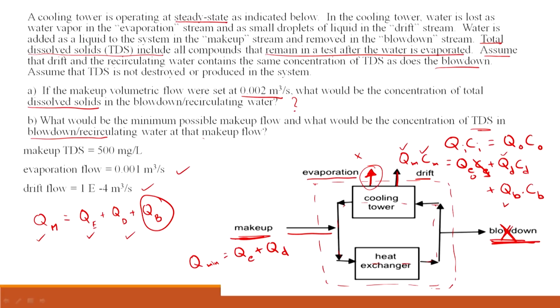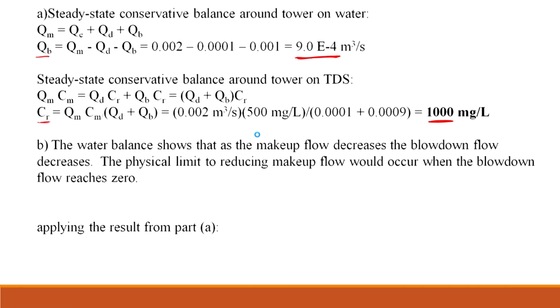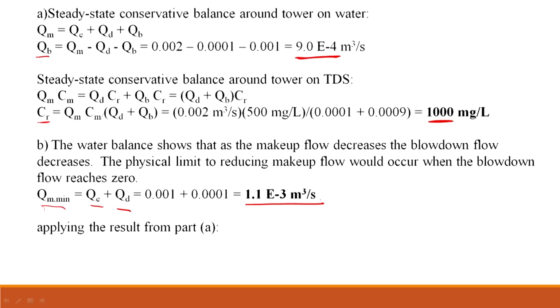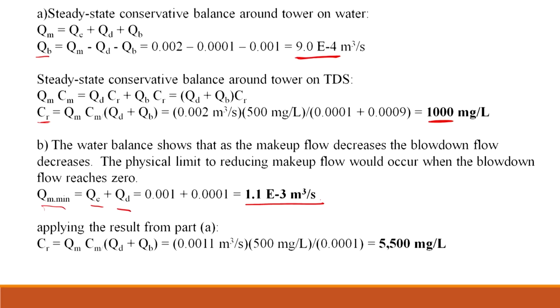So what is the TDS in the makeup flow? Let us calculate. Q minimum is Q evaporation plus Q drift, which is 1.1 into 10 power minus 3 meter cube per second. Applying a similar mass balance as before, but here the blow down is 0. I may have a minor error there, you can calculate and clear that up yourself. So it looks like the TDS in the blow down, or the recirculating water here, is 5500.